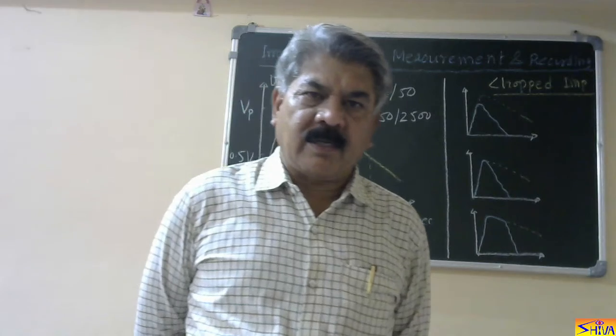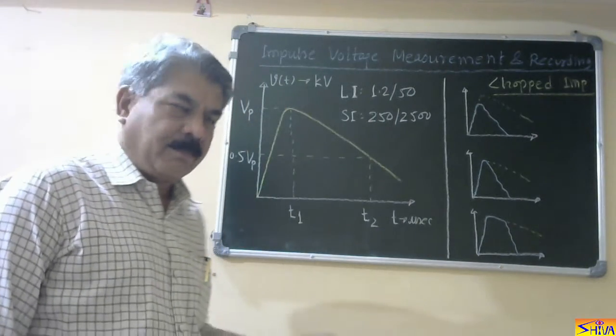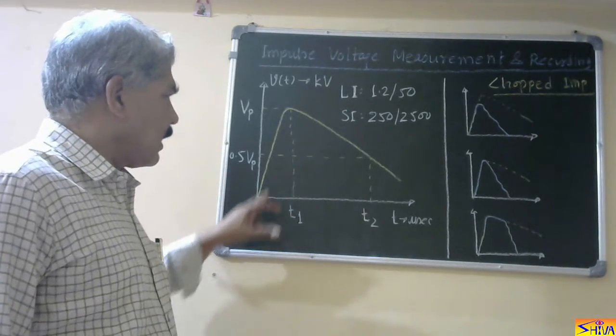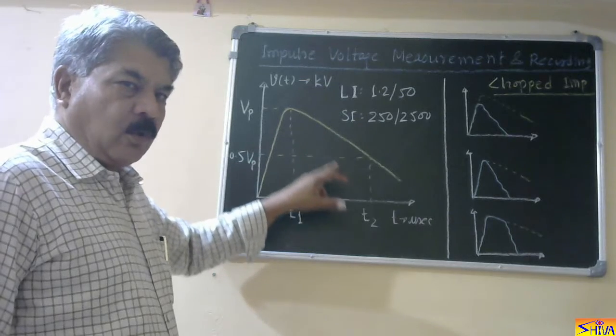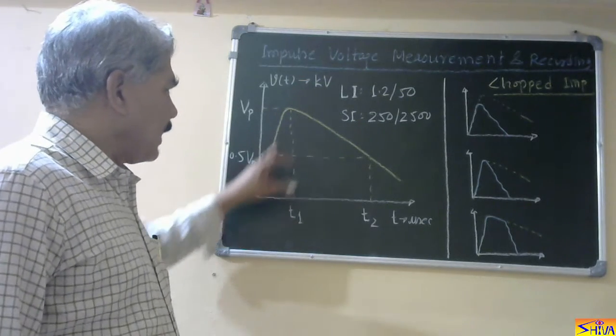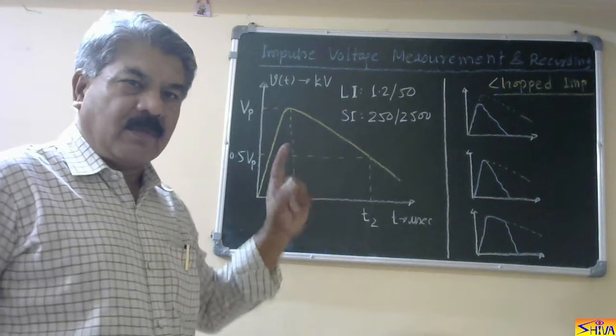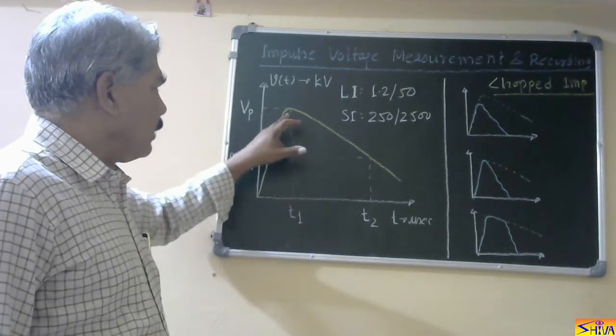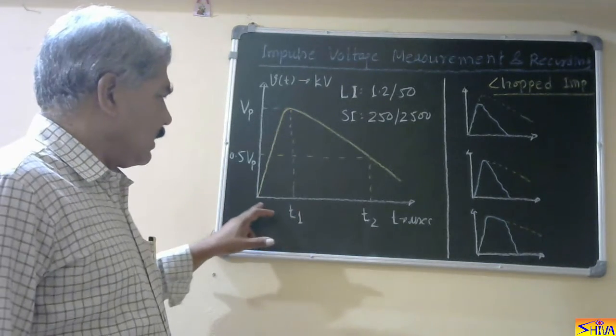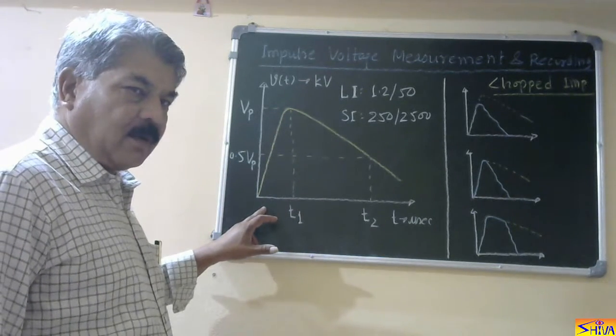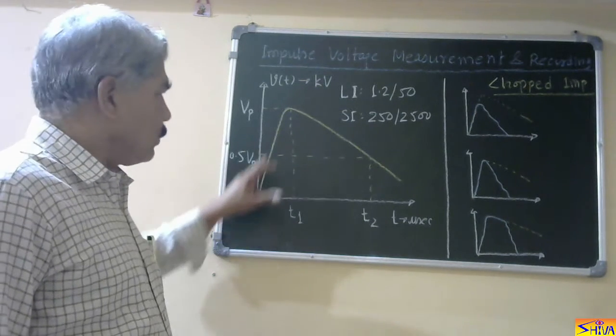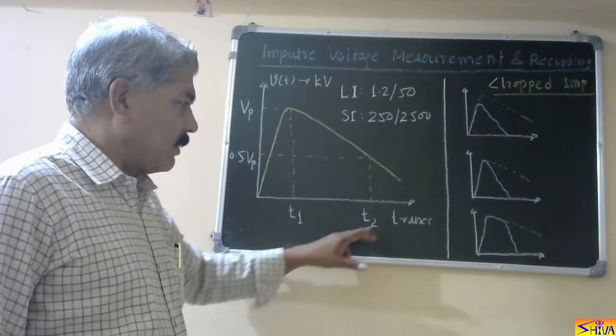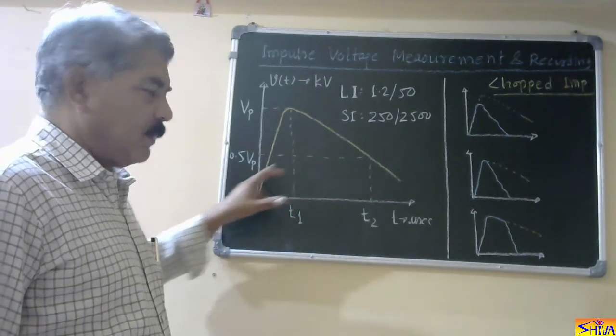Basically, recording is important. Let us take a brief review of what is an impulse wave. Impulse wave is characterized by sharp rise in the amplitude and relatively slow decay. This rise and decay are in microseconds and this is a one-shot voltage. Now, impulse voltage is defined by three parameters: peak value, T1 and T2. T1 is called rise time or front time — it is the time required by the impulse wave to reach the peak value. T2 is tail time or decay time — it is the time required by the impulse wave to reduce to 50 percent of the peak value.